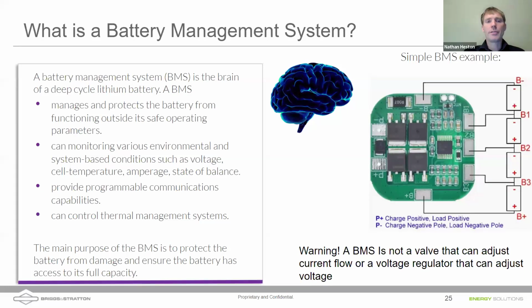It can also monitor various environmental and system-based conditions, such as the voltage of the charge controller. So if you have a malfunctioning charge controller, the BMS can shut down that connection to the charge controller and protect itself. It can monitor cell temperature, and if the battery cells get too hot, it can slow down the discharge rate or the charge rate. It can monitor the amperage and make sure that amperage doesn't exceed what the battery can handle.